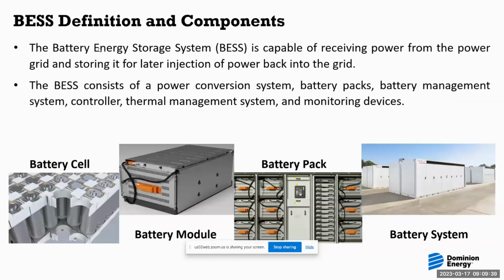A battery energy storage system, or BESS, is capable of receiving power from the grid, storing it, and later injecting it back to the grid. A BESS consists of a power conversion system, probably the most important piece, which takes the direct current stored in the batteries and inverts it to become alternating current for injection onto the grid. That power conversion system also takes alternating current from the grid and rectifies it to direct current for charging the batteries. The system also consists of the battery packs themselves and a battery management system.